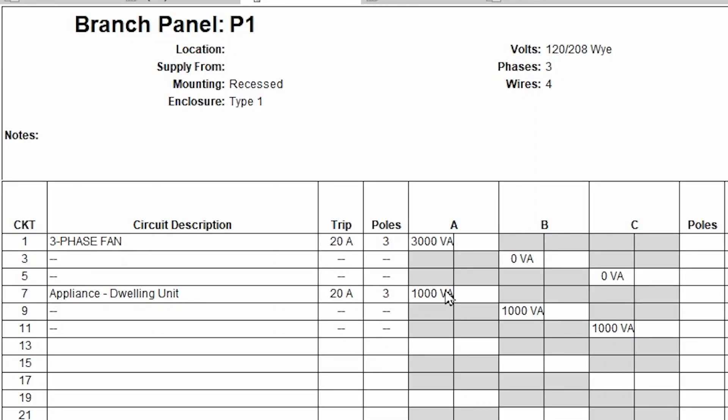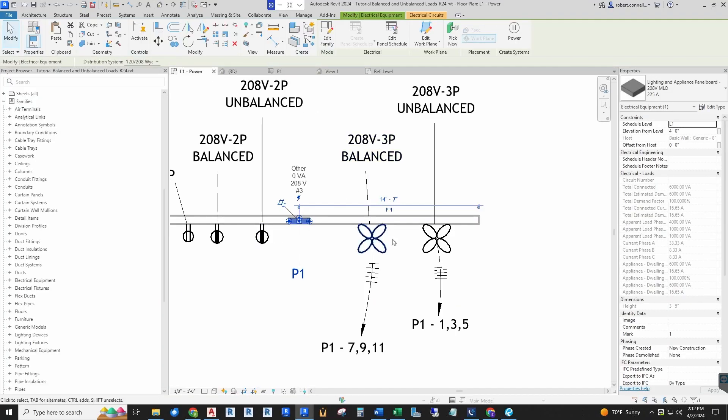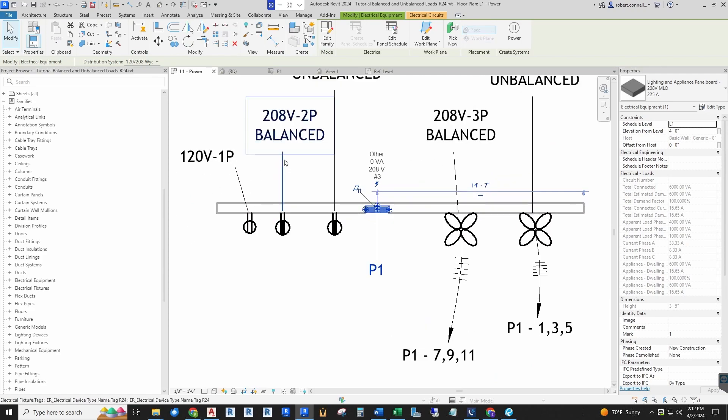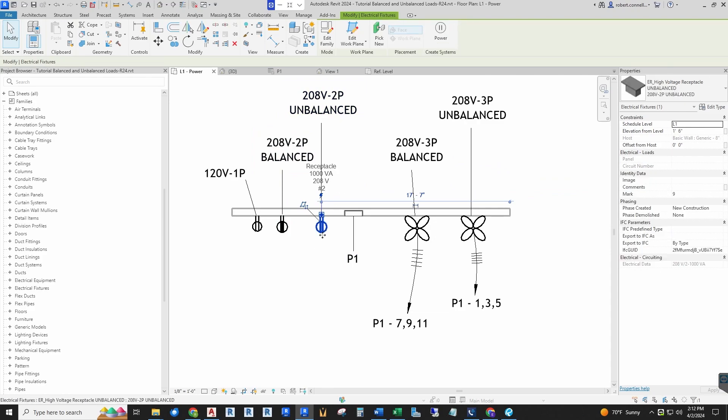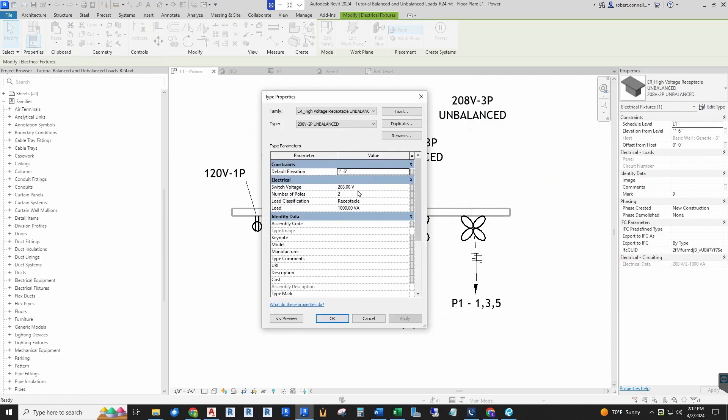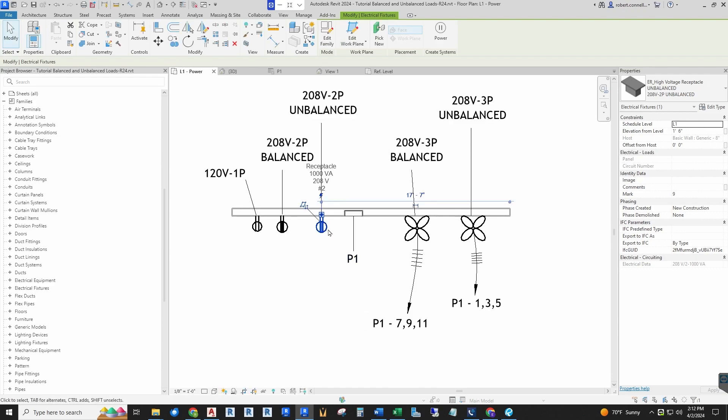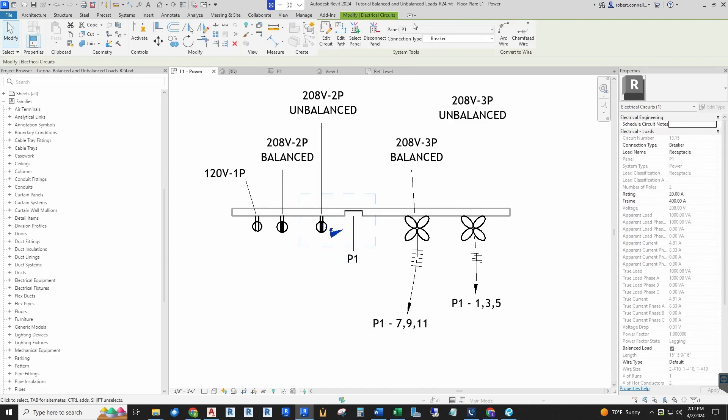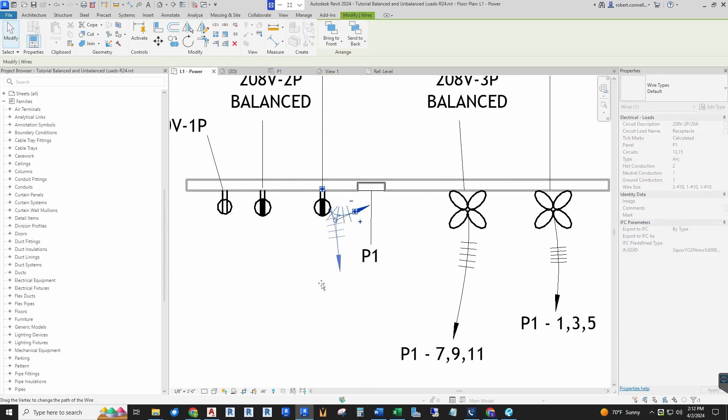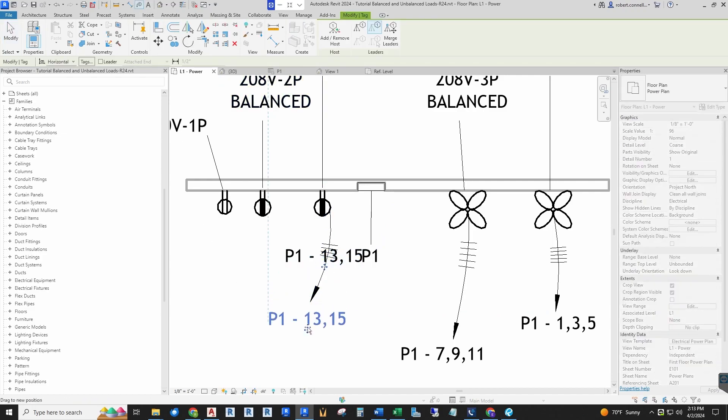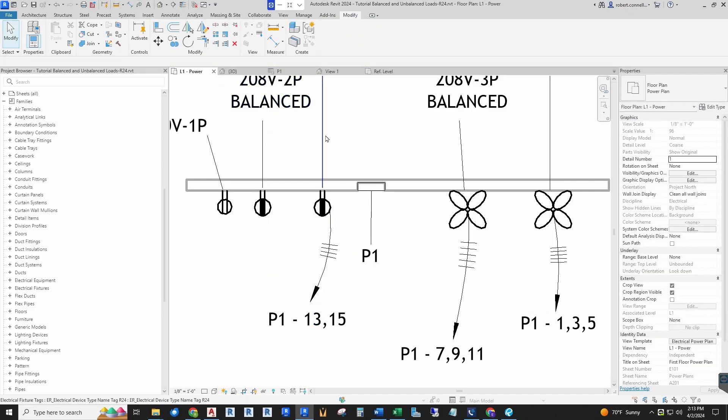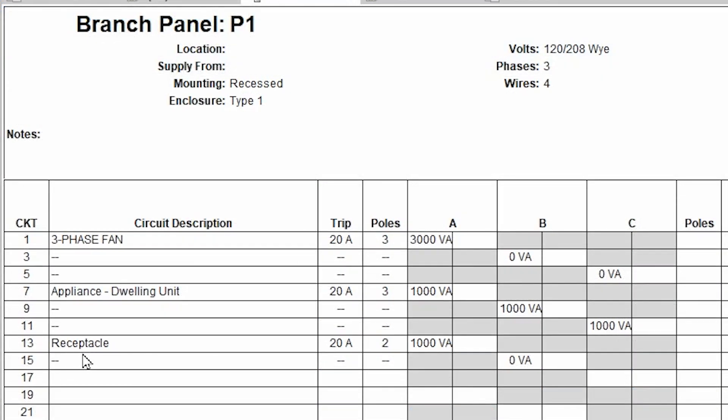Now the same thing will happen in a two-pole circuit. If you look at something like these two-pole receptacles, we have a balanced and unbalanced. If you connect the unbalanced receptacle—it's a two-pole 208 with a load of a thousand—if we connect this to the panel, power panel P1, go ahead and get our arc in there so we can tag it. It is connected to panel P1 circuits 13 and 15. Look at panel P1, circuits 13 and 15. There the unbalanced load only puts it on one phase.